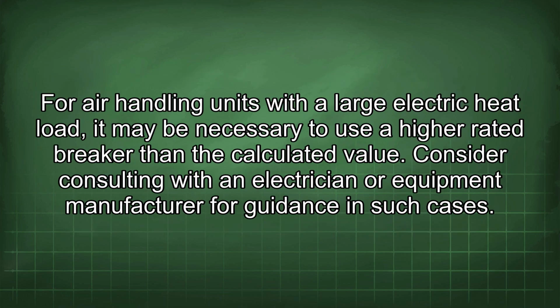For air handling units with a large electric heat load, it may be necessary to use a higher rated breaker than the calculated value. Consider consulting with an electrician or equipment manufacturer for guidance in such cases.